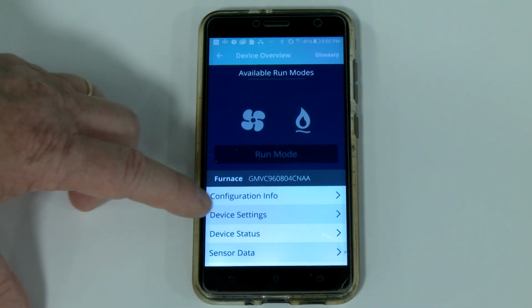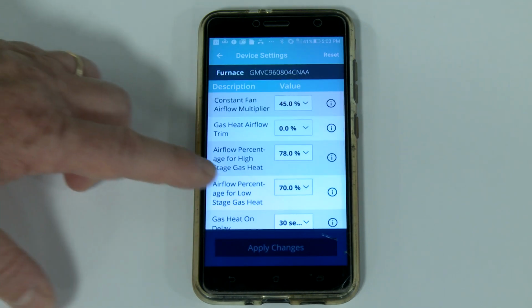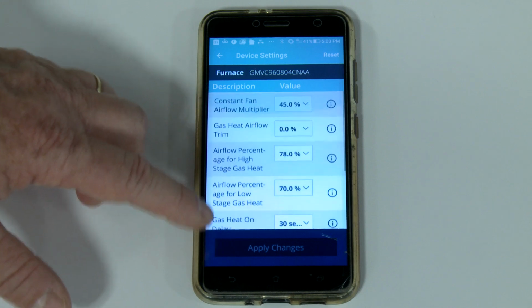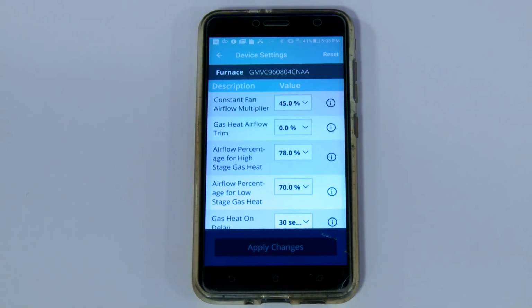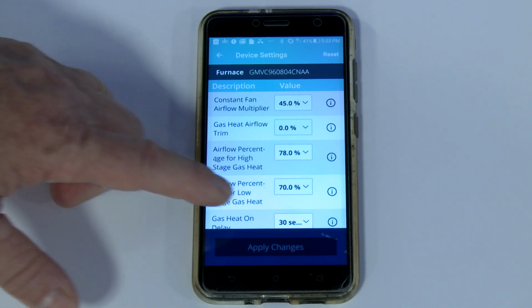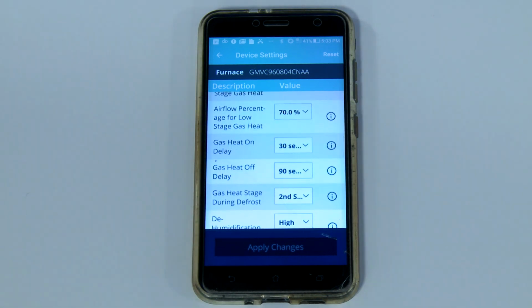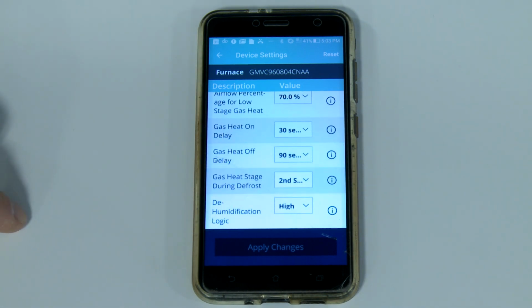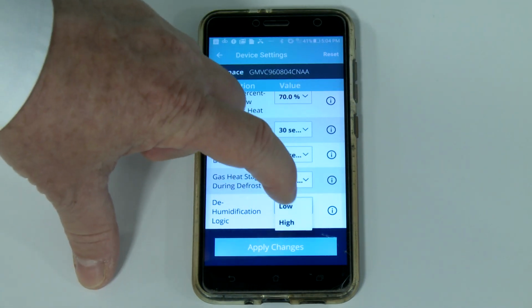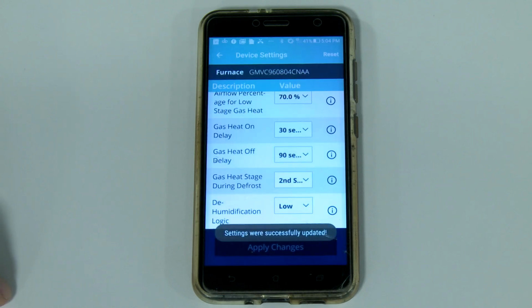Device Settings allows you to make several adjustments to the HVAC system. While the equipment is designed to configure automatically during the initial installation, this is the area where you can make fine-tuned adjustments. For example, you can adjust how the staging algorithm works on the gas furnace. Further airflow, gas heat on delay, dehumidification logic, and several other options are available for minor adjustments. For example, if you wanted to make a change to dehumidification logic, touch the drop-down menu next to it, change it from high to low, hit Apply Changes, and that change will be successfully saved into the system.